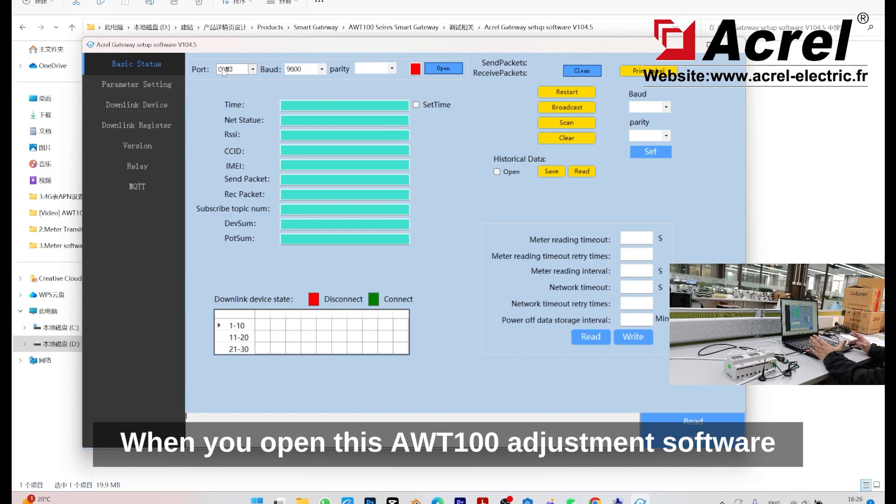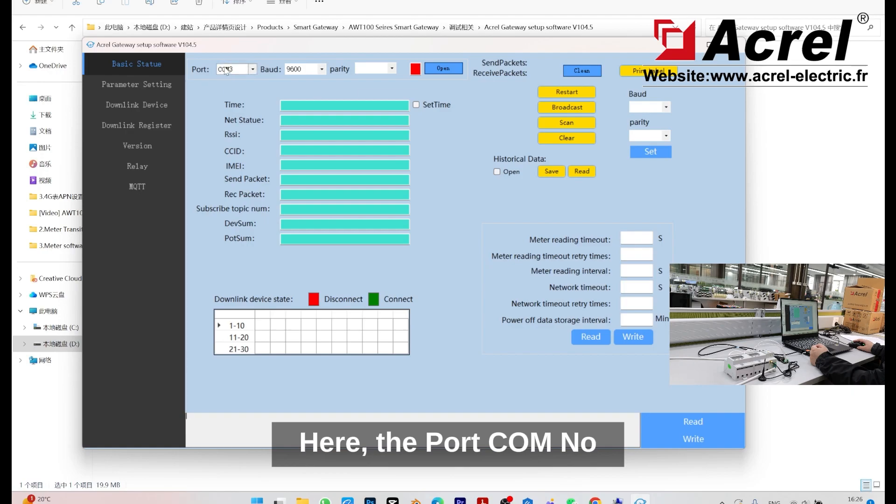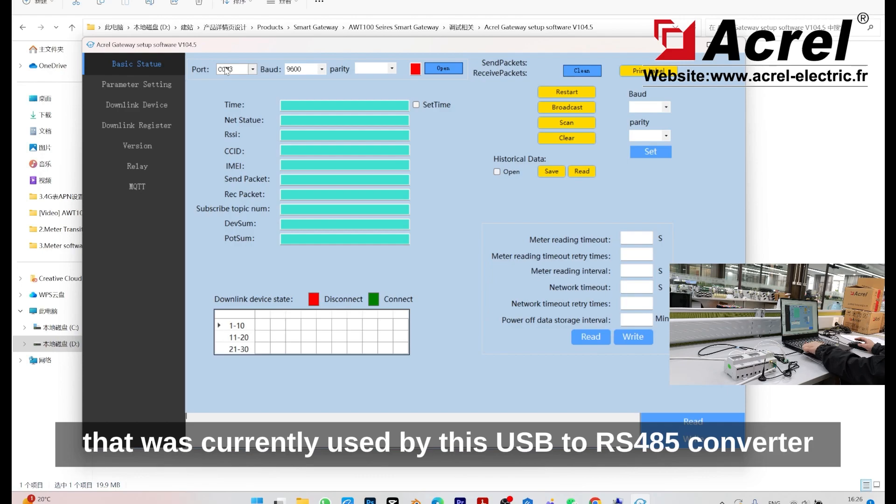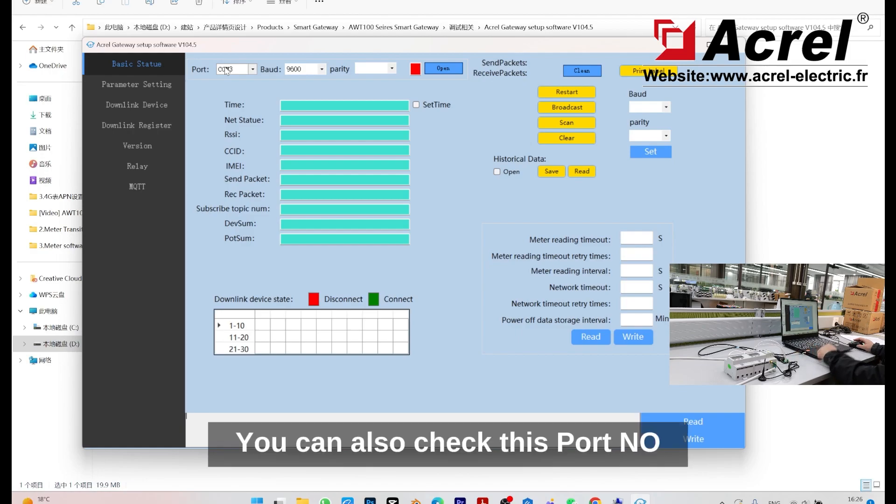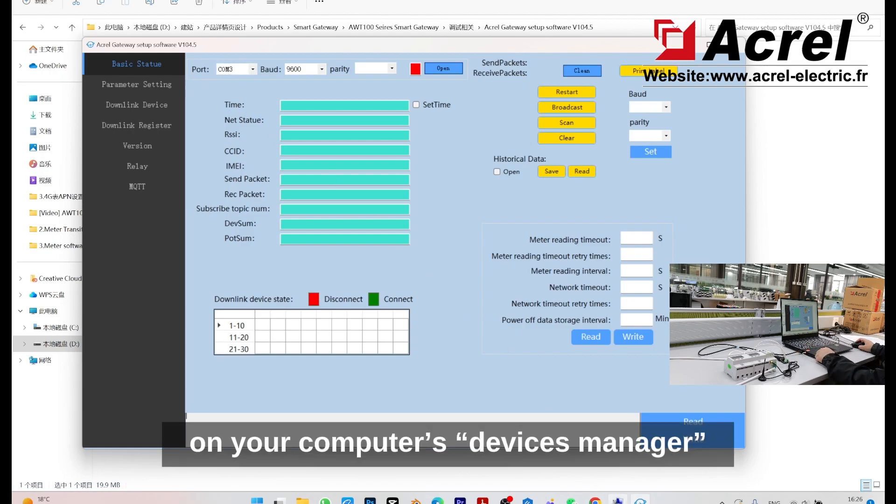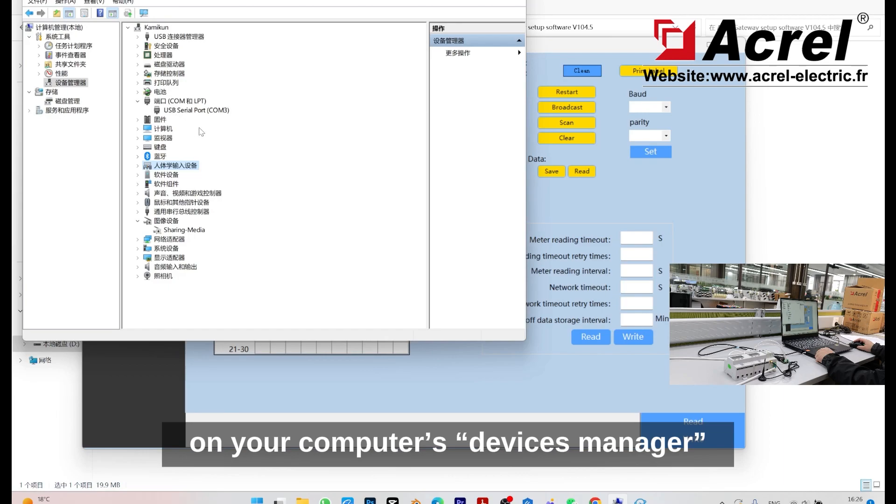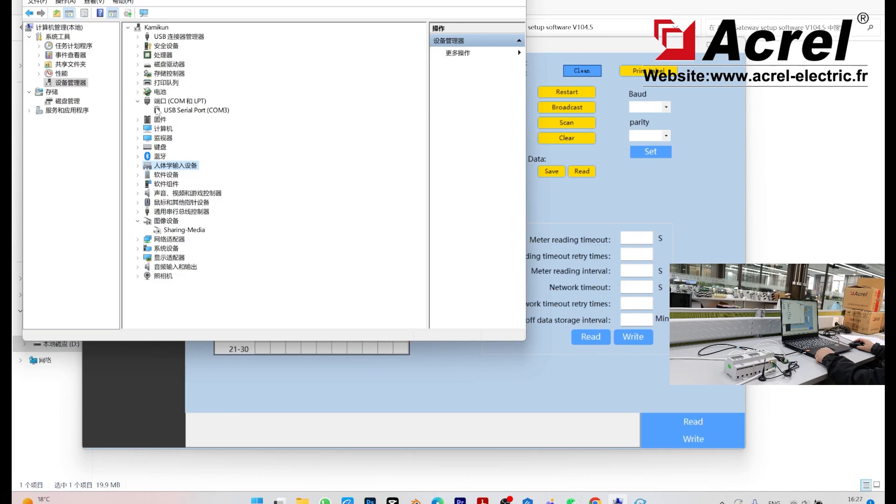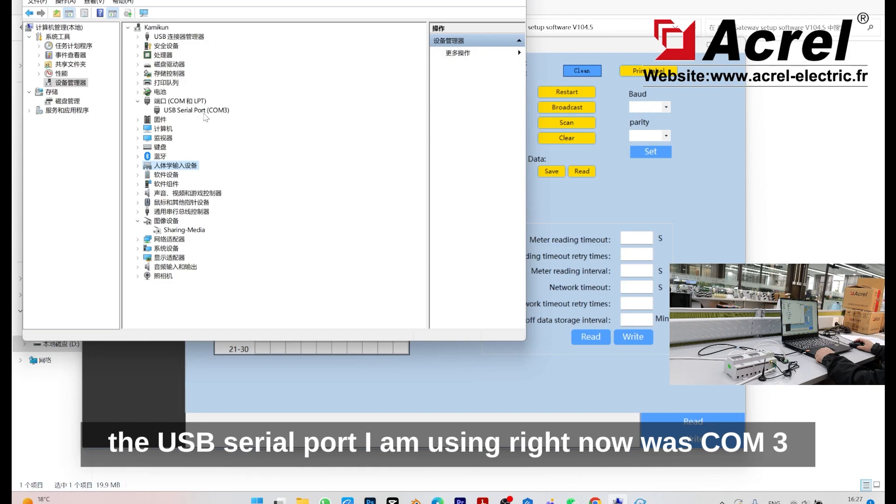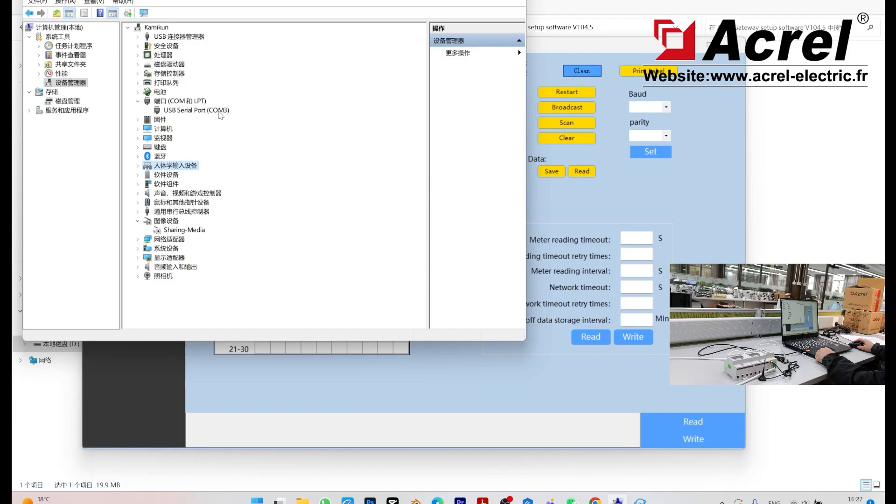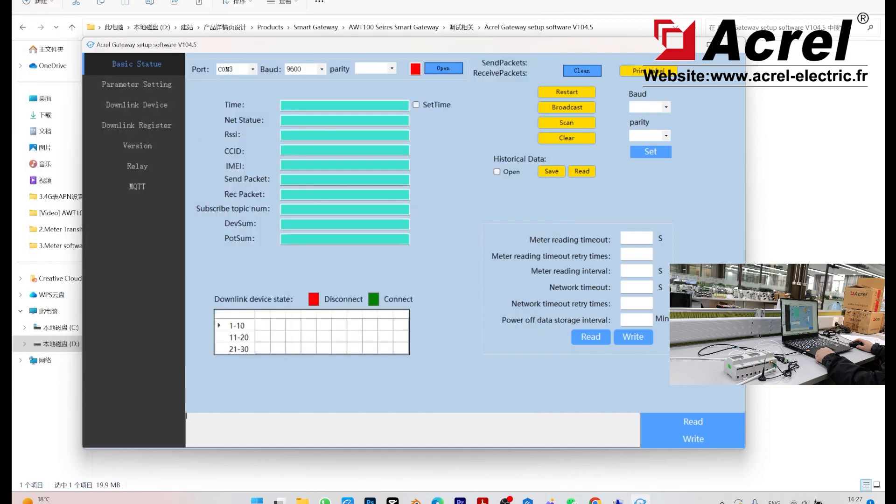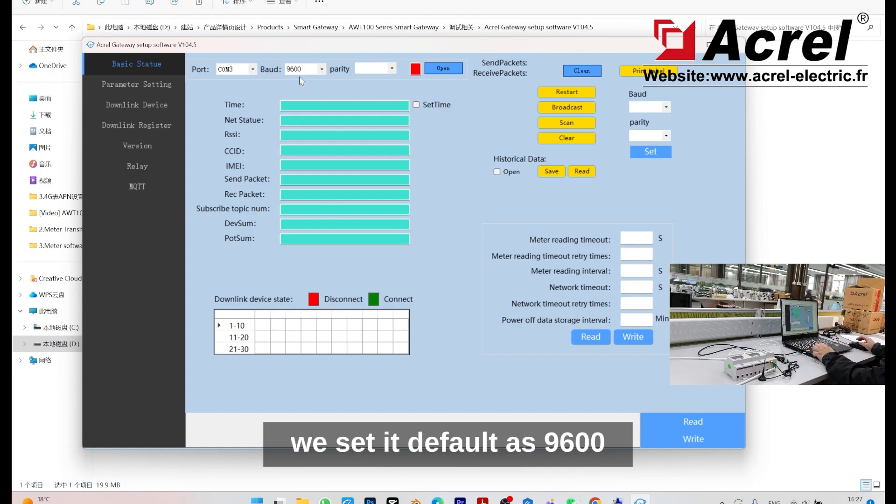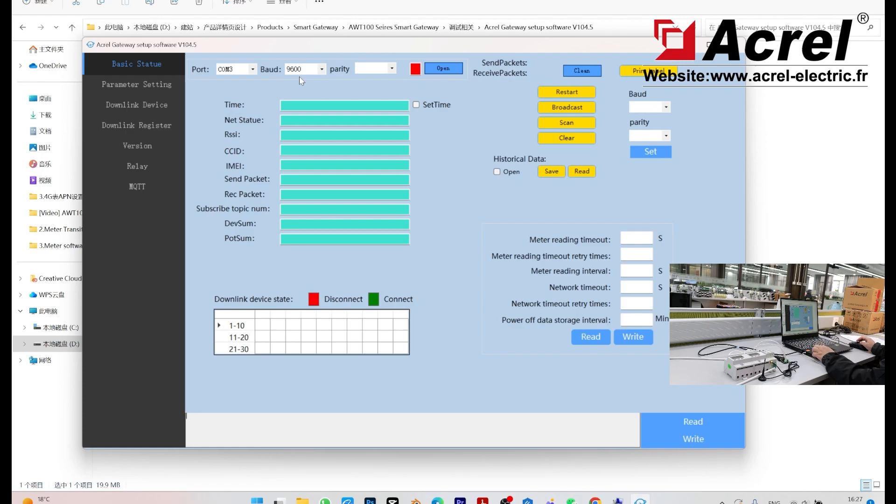When you open this AWT100 software, the port column number should be the same as the column number currently used by this USB to RS485 converter. You can check this port number on your computer's device manager. As you can see here, the USB serial port I'm using right now is COM3. For the baud rate, we set default as 9600.